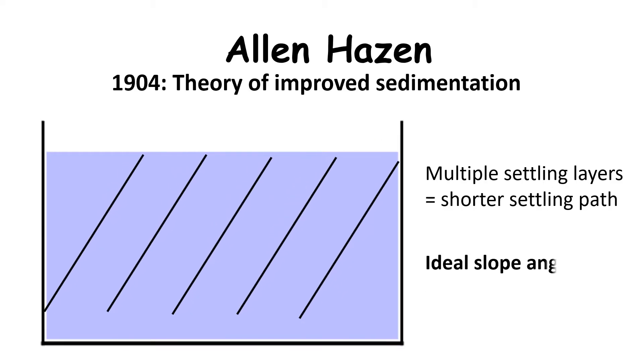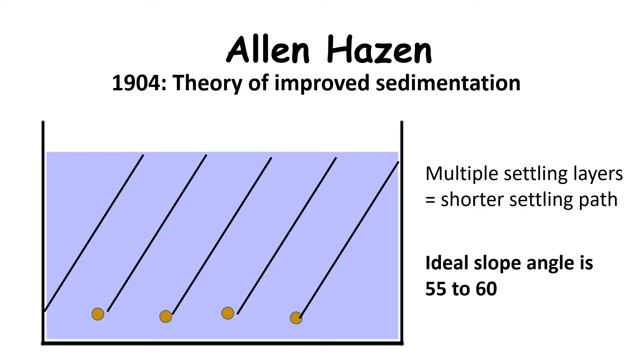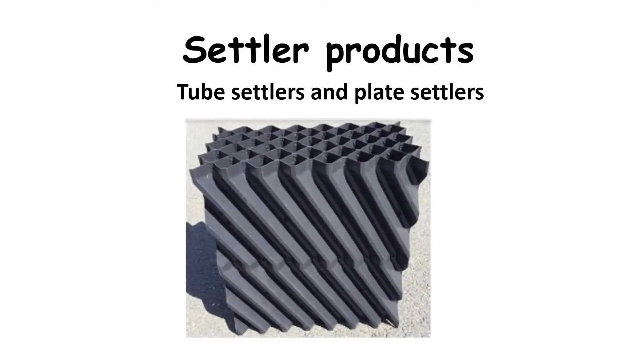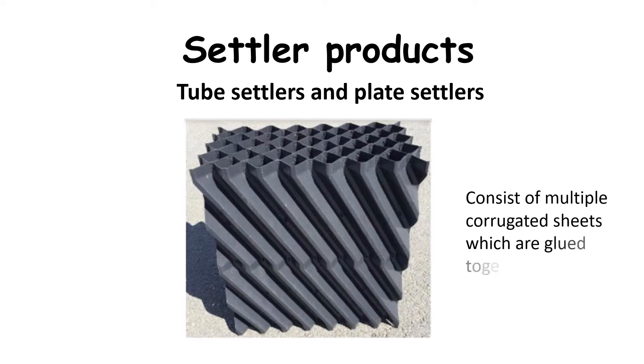The ideal angle of the surface layer is between 55 and 60 degrees. The surface layers are provided by tube settler or plate settler equipment. Tube settlers are usually made of PVC plastic and consist of multiple corrugated sheets which are glued together to form rectangular blocks with multiple channels.